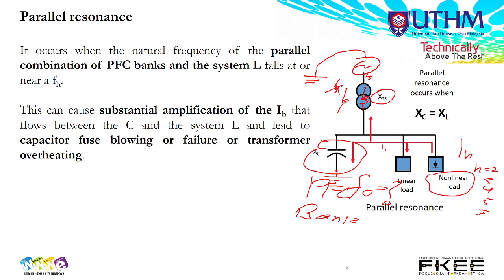That's why it's called parallel resonance. Parallel, seen from the source of resonance - the source of resonance is also connected to ground, and this one is also connected to ground. Resonance comes from the harmonic from the non-linear load. Seen from the non-linear load, it's parallel with the C and L of the system. That's what it means, that's why we call it parallel resonance.